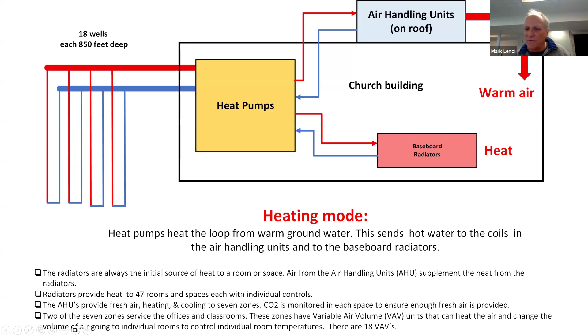The cooling mode is the interesting part, one we underestimated initially—we don't actually use the heat pumps. In this mode, we take cool water out of the ground, it goes right up to the roof, makes cool air, goes down to the rooms and back down to the ground. So in cooling mode, the only cost is running the pump circulating the water and the blowers. That's it—it's almost free. Free doesn't mean free as in money, that's a different technical term. But that's why we overestimated the cost of our utilities running this thing.